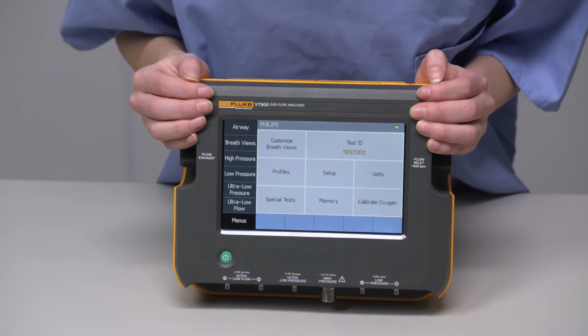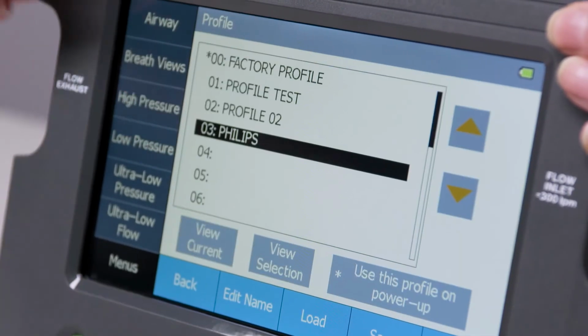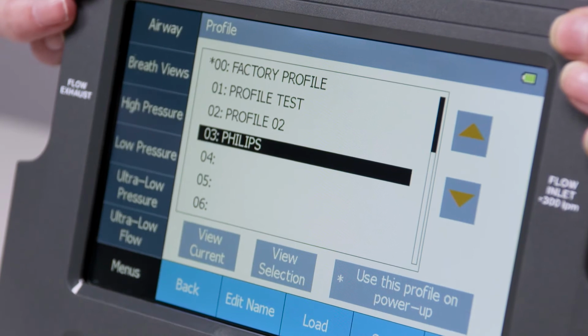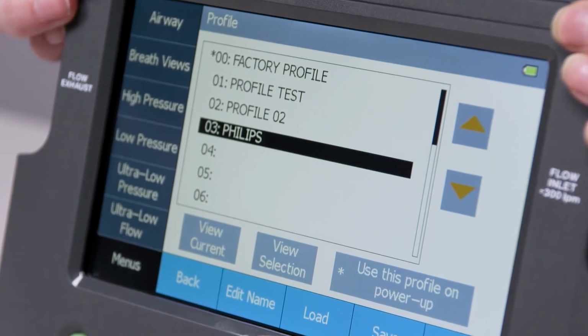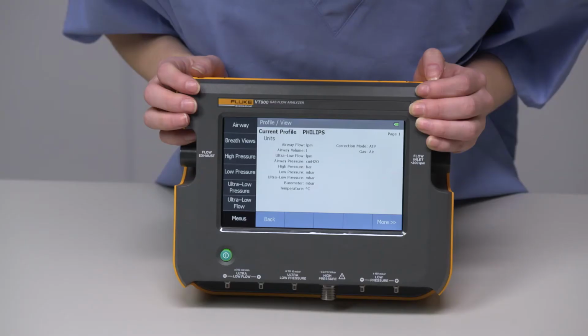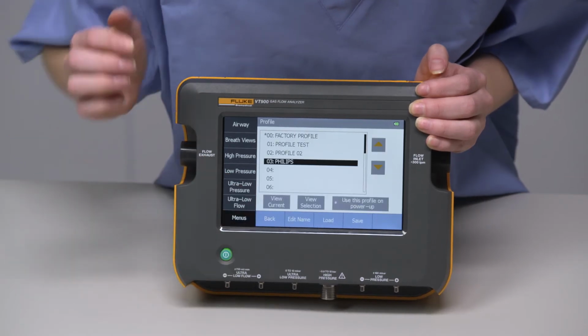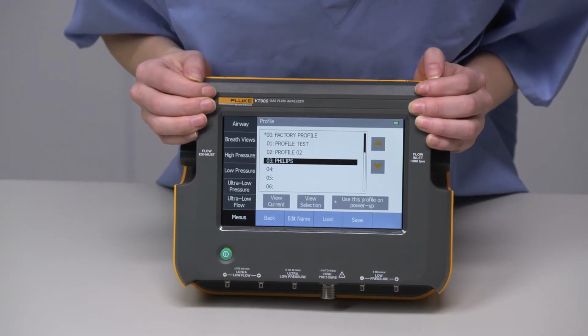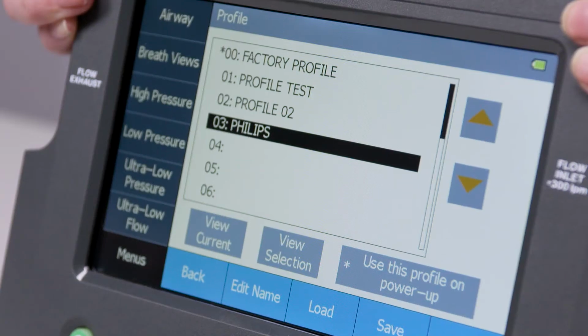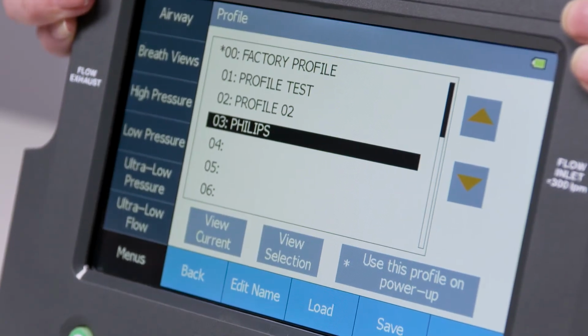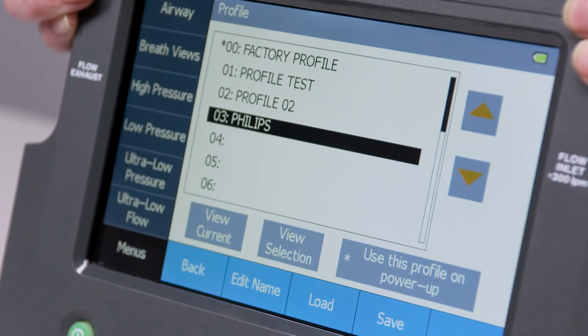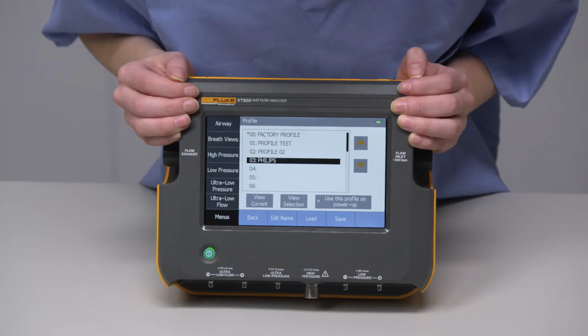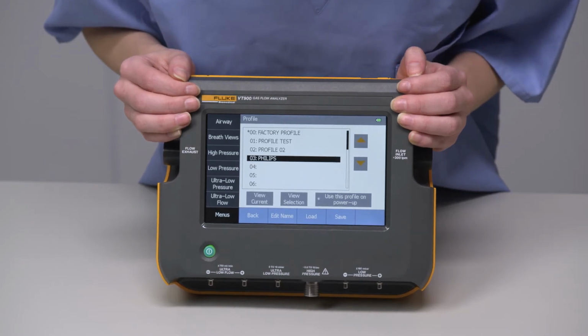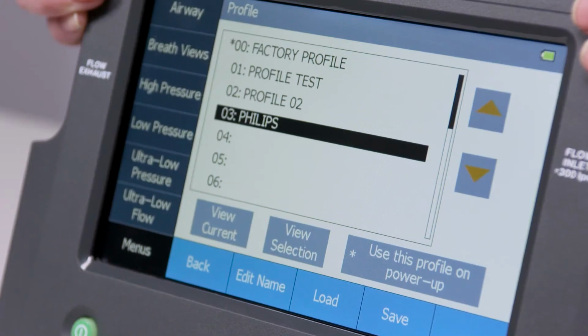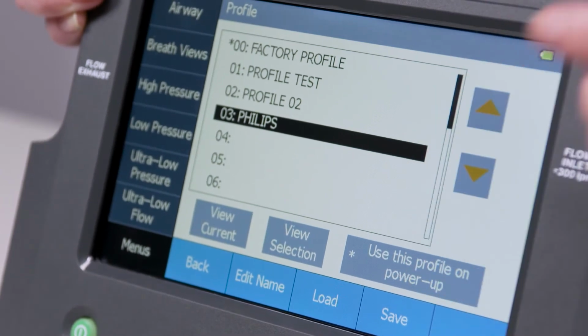From the menu setting, select Profiles. We can look at the changes we've made and our current setup by pressing View Current. Let's go back and save this as a profile. In the future, when we have to use this same setup or test this certain ventilator or other gas flow device, we don't have to redo our test setup. We're going to select which number we want to save it as. Let's say we want this to be the third profile. We highlight the third profile and hit Save.